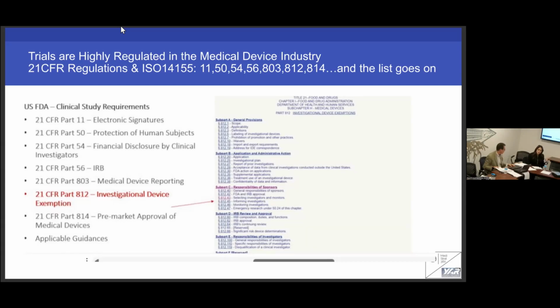So this is another watch out for folks: be really good about recognizing that if your plan is to generate clinical data, you want to make sure that you are taking the time to meet with somebody who knows what the regulatory requirements are beyond whatever it is that you're doing at your institution to get that documentation. And source data verification is a great example of that. If you're running a clinical study to get a PMA cleared, we're required to have quality plans in place that say we verify the data and ensure that we're doing regular checks for specific data that's important to that study. You don't have to do that when you're running a clinical study within your institution.